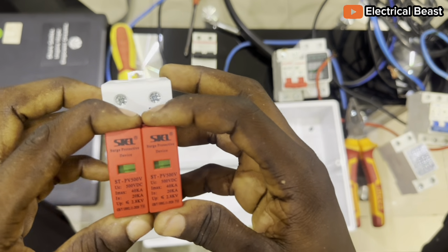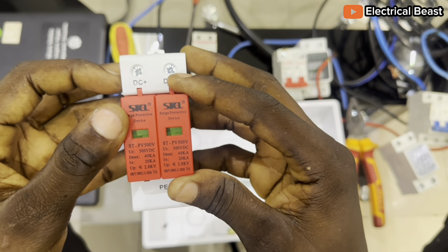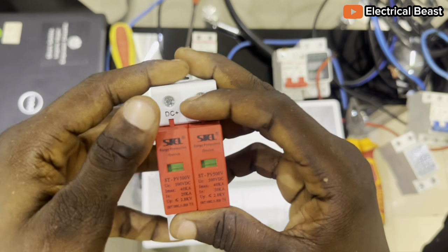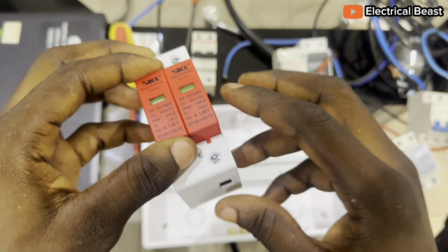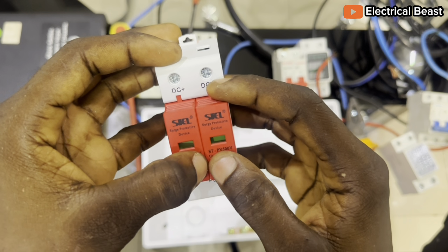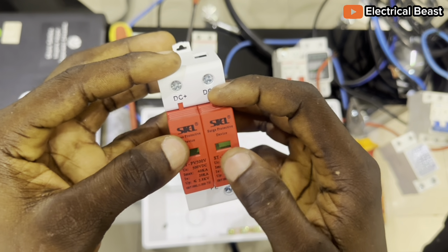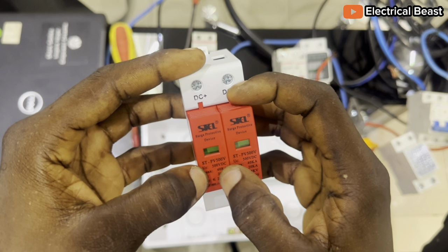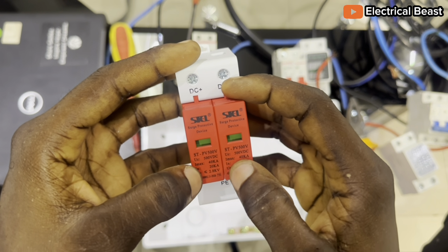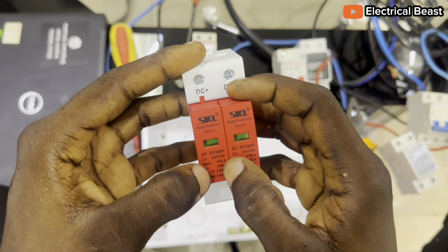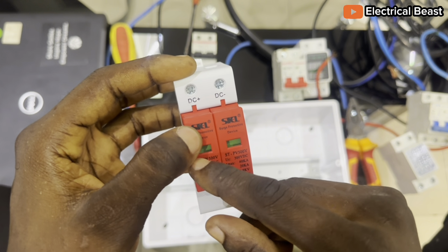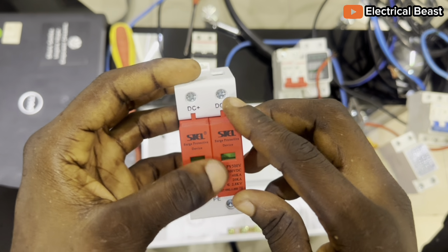This is a surge protective device, as you can see from the scale. Normally, it doesn't conduct current, but when there's a sudden voltage spike, it diverts that surge to the earth through the grounding terminal right here. You can see the ratings. You can see the UC, 500 volts DC, the maximum voltage that the SPD can handle. Then we have the IMAX, the maximum surge current it can divert, 40 kiloamps. Then the nominal discharge current, which is 20 kiloamps. Then we have the voltage level that may appear across the SPD during a surge.